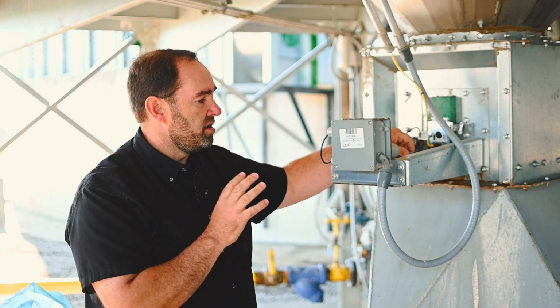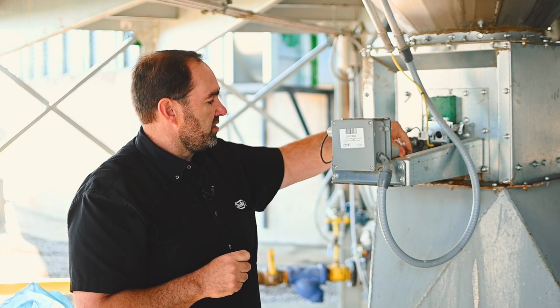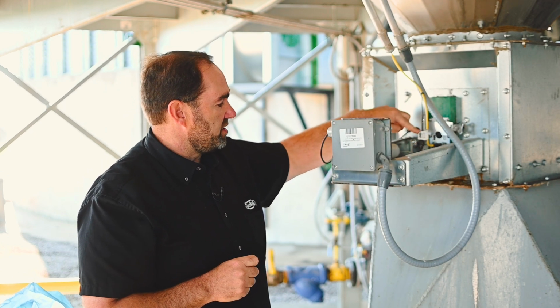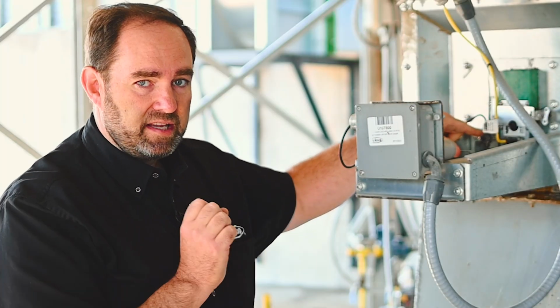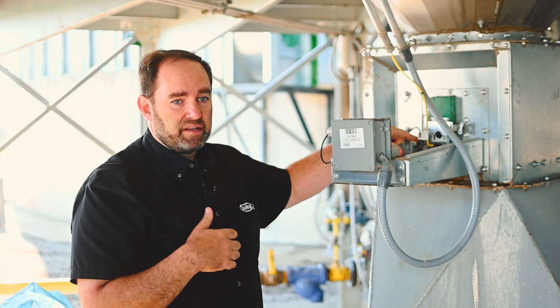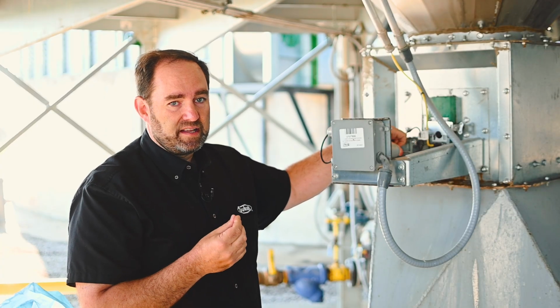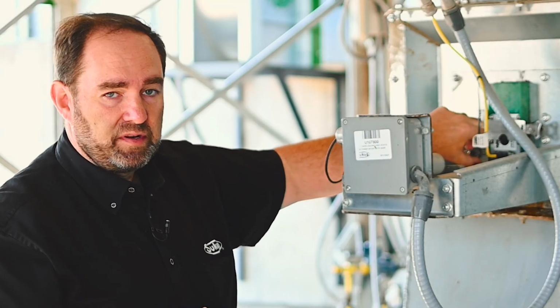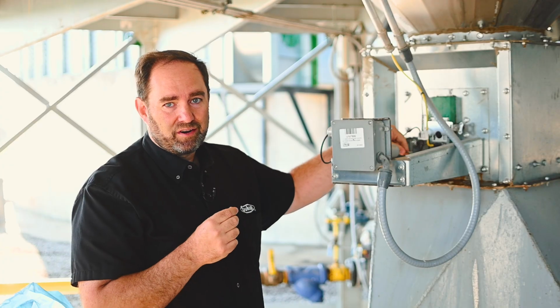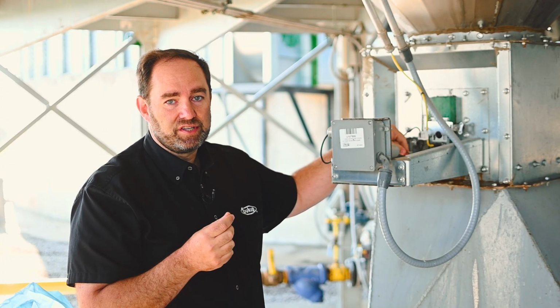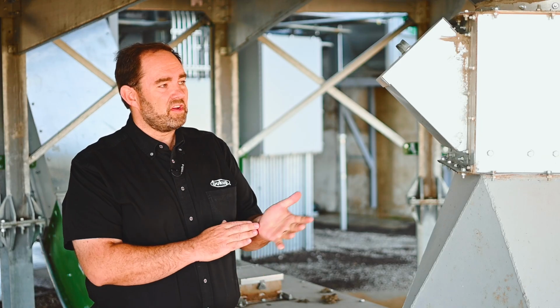So we turn the unload on, we should see this start to move. There is a target on here and a proximity switch that just verifies that the gate is opening and closing, and the PLC or the control system needs to see that proximity switch. The gap between the prox switch and the target needs to be about a credit card's width, or about 1/8 of an inch to work properly. Okay, on the other side of the moisture sensor, there's a place where you can take a sample of grain coming out of the discharge of the dryer.